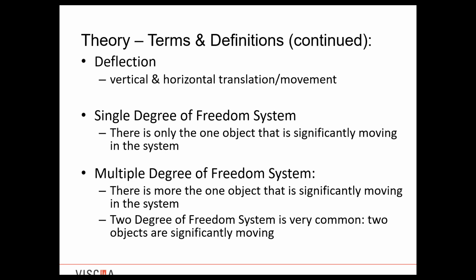But you have a single degree of freedom system. There's only one object that is significantly moving in the system. If you could picture a slab on grade, a concrete slab on soil that's perhaps outside an office building or a hospital doctor's office building, and you have a pump or a piece of equipment for air conditioning that's bearing on that slab on grade. The fans and motors inside are moving, and you probably have some internal isolation within that piece of equipment, but preferably the slab on grade is not moving. So the only thing that has the moving parts is your equipment. Your slab on grade is stationary. So that example would be a single degree of freedom system.